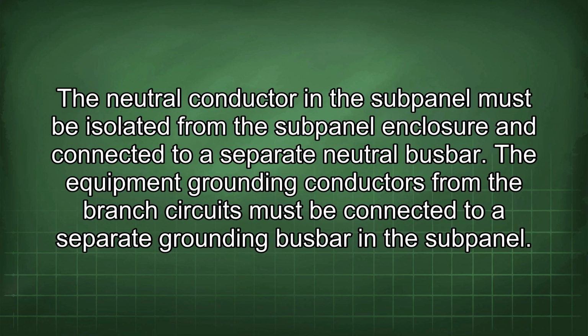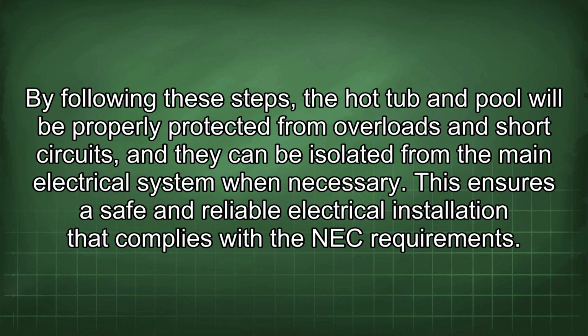The neutral conductor in the subpanel must be isolated from the subpanel enclosure and connected to a separate neutral busbar. The equipment grounding conductors from the branch circuits must be connected to a separate grounding busbar in the subpanel. By following these steps, the hot tub and pool will be properly protected from overloads and short circuits, and they can be isolated from the main electrical system when necessary. This ensures a safe and reliable electrical installation that complies with the NEC requirements.